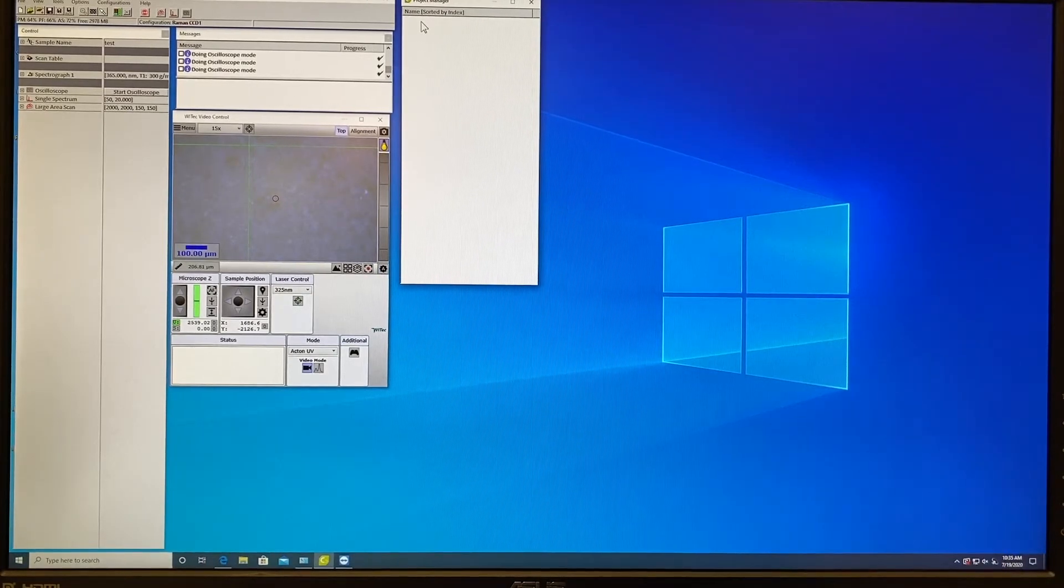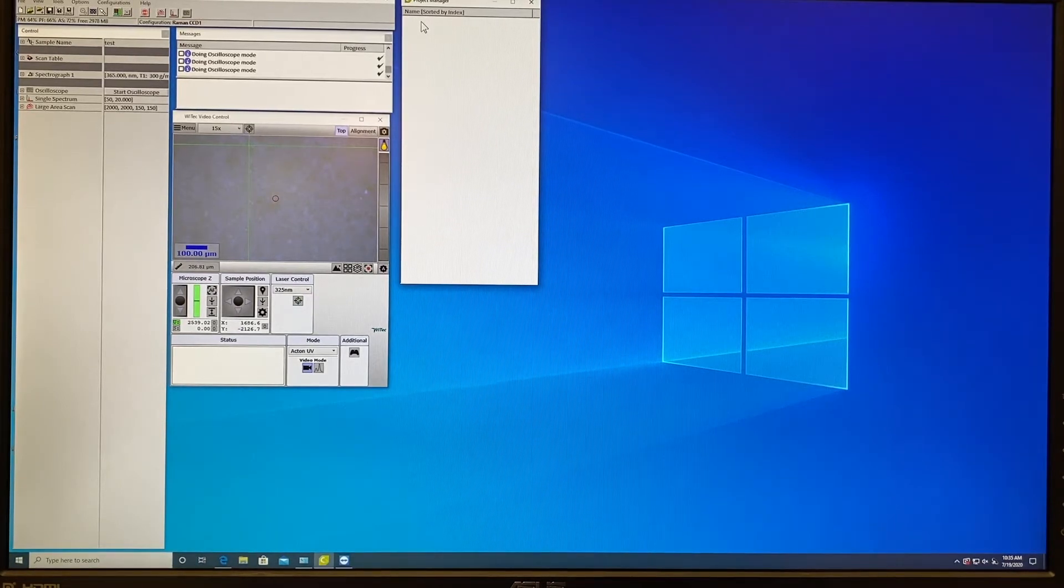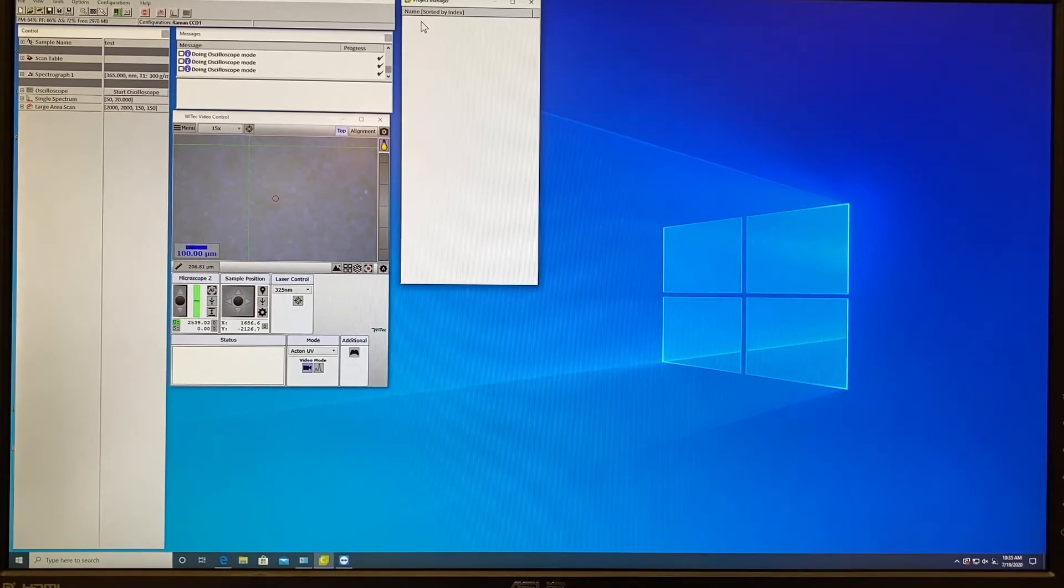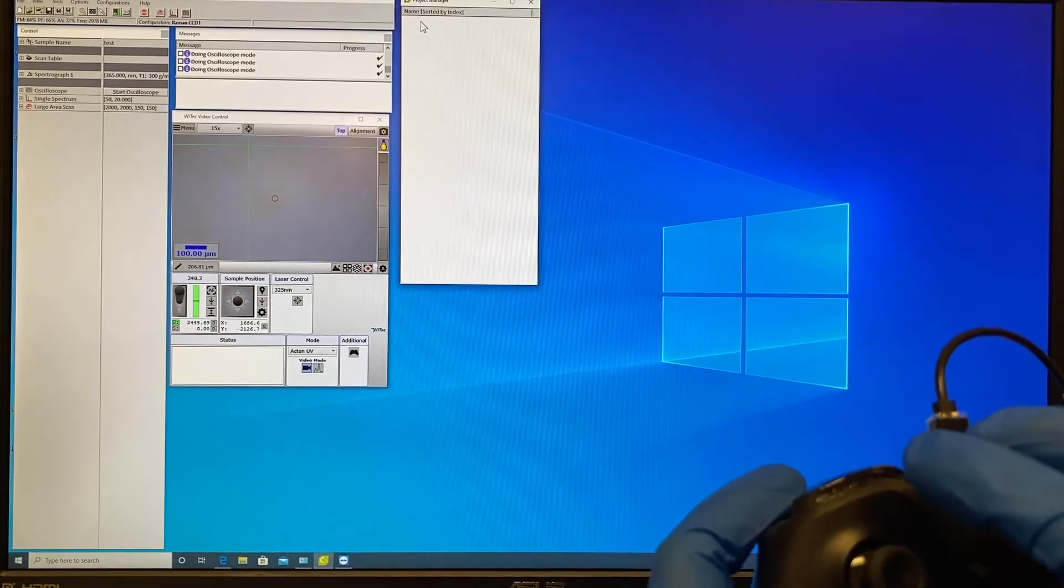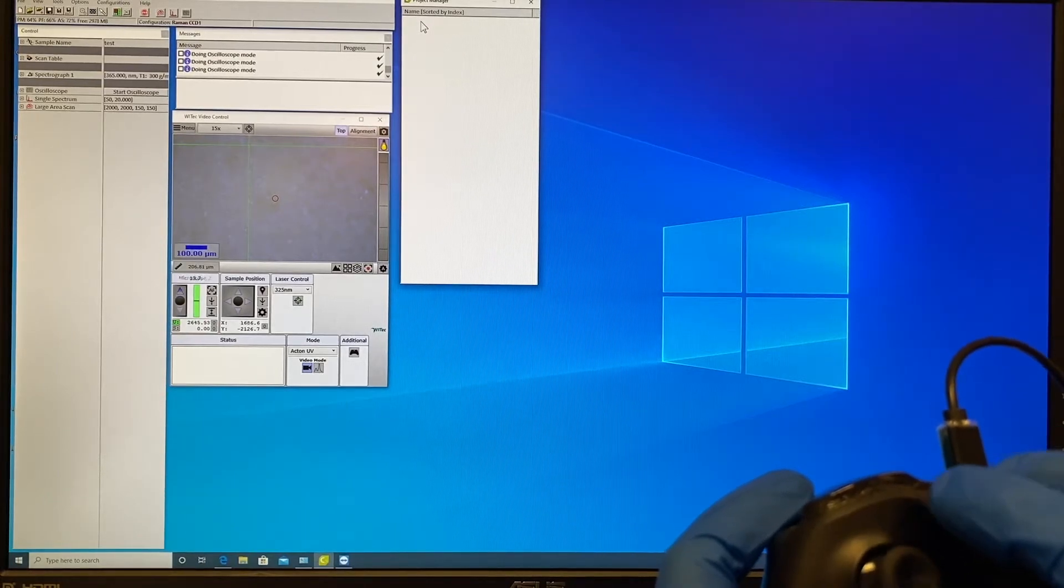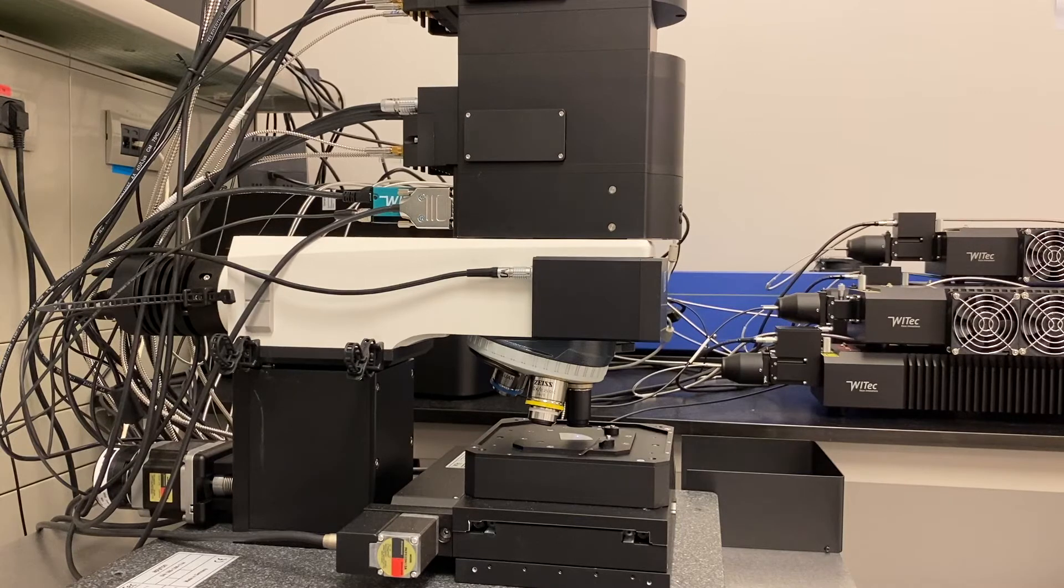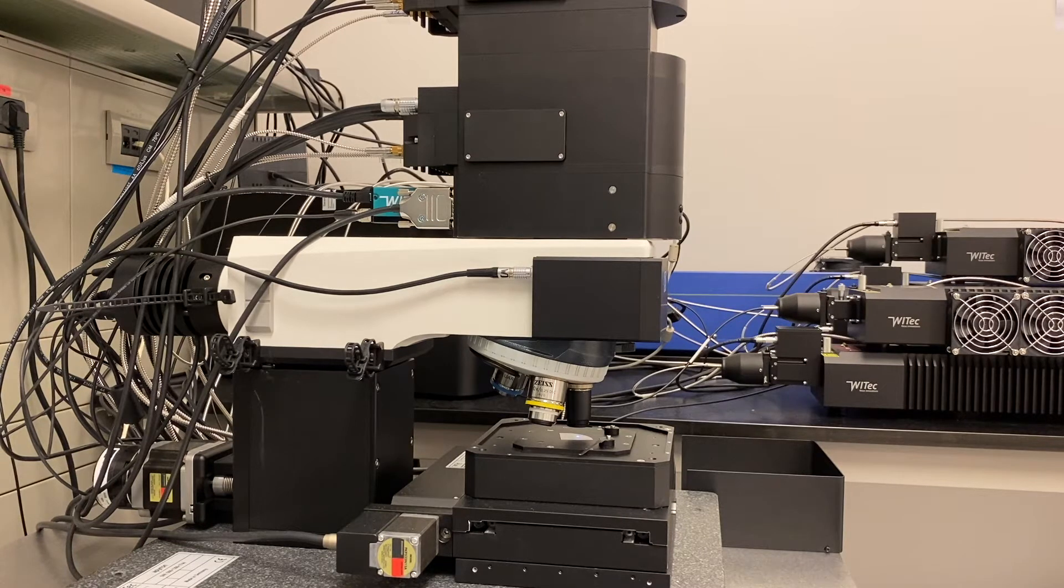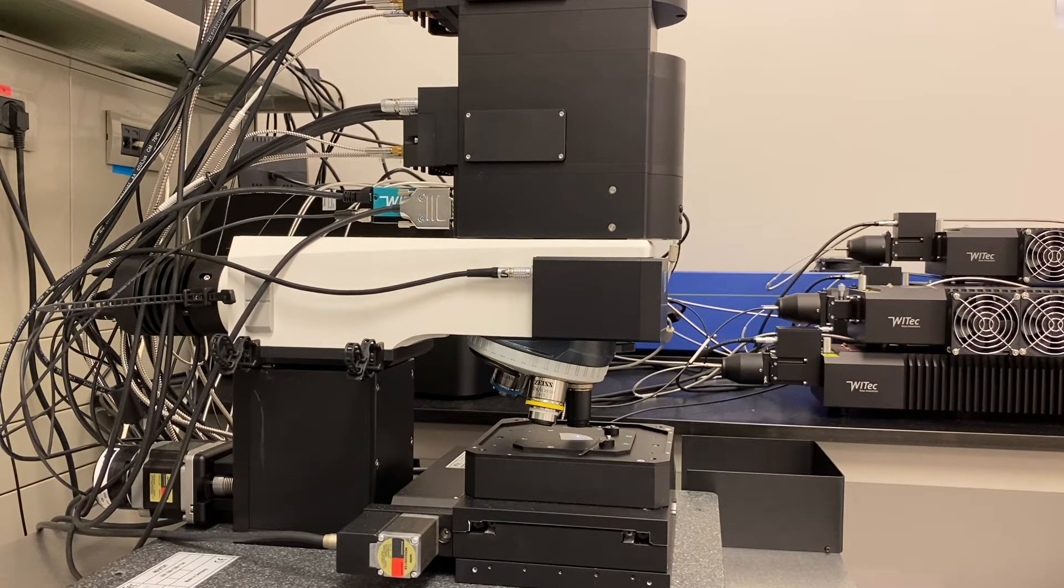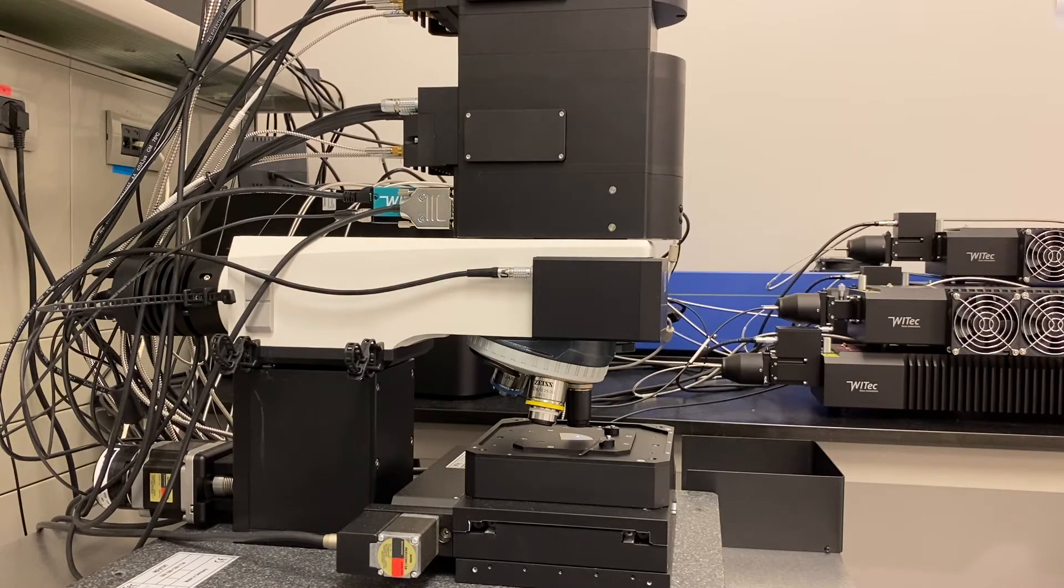You can see on the video control window that we achieve the focusing distance. Unfortunately with UV objective it's hard to see the surface. So you may move down with the Z knob to look if the picture gets more clear and focused. It seems this is a good point. While you do visual focusing you should never put the safety lid back because you need to observe the distance between the objective and the stage and to see if it's really corresponding to what you see on the video control window.